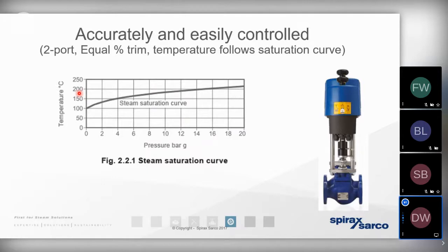But if we only require a temperature of, let's say, 130 degrees at the process, this tells us that we can achieve that temperature by manipulating the pressure down to 2 bar gauge. So that's the first benefit of having that pressure temperature relationship.